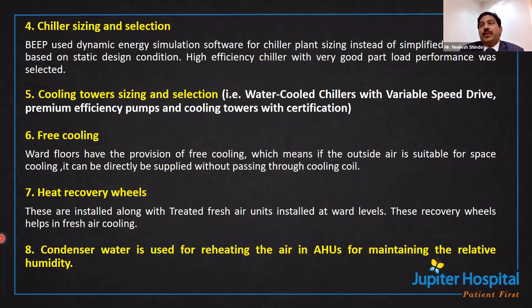Now, very important: around 50% of the energy is dependent on HVAC. Out of that HVAC 50%, 19 to 20% depends on the chiller. So chiller sizing and selection is very important. In a city like Pune, or most places in healthcare, the load is always a dynamic load.